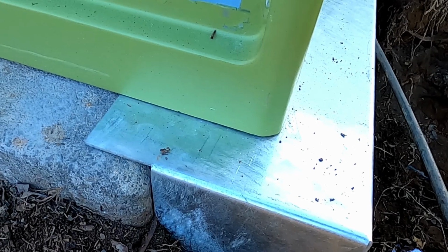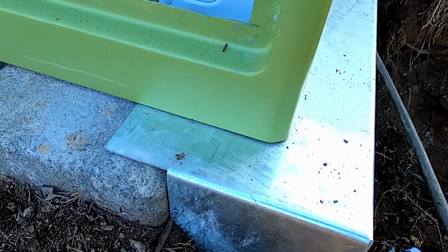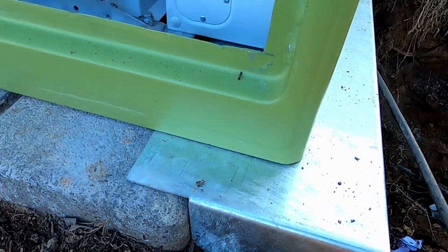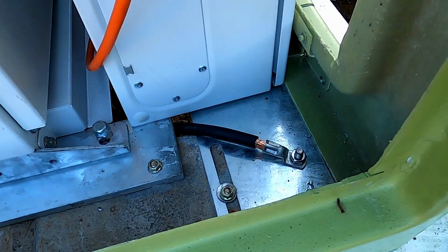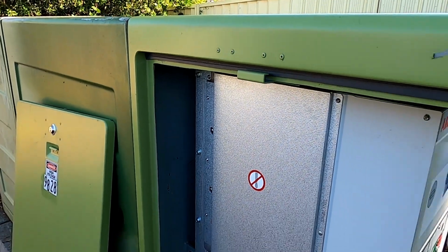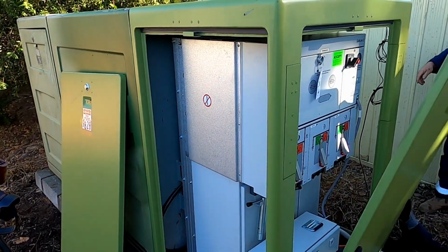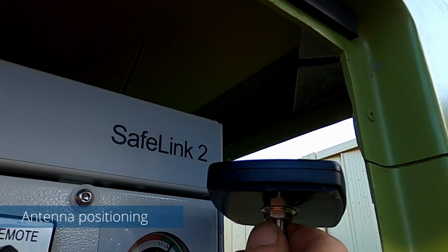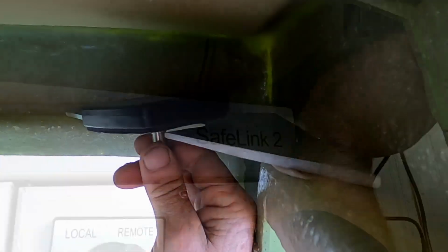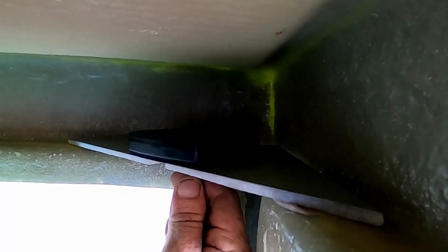The steel plinth extension should be bolted in place prior to fitment of the cubicle. It should also be connected into the earth grid of the substation. Install the new cubicle. Remove the backing paper from the self-adhesive tape on the antenna. Then install the antenna to the shelf in the top right corner of the cubicle.